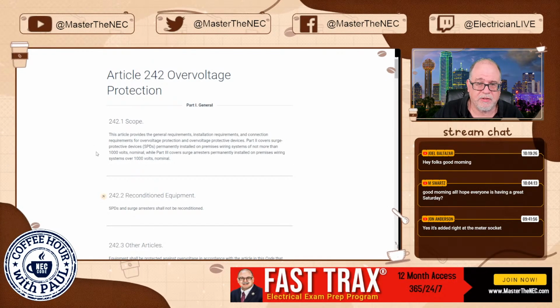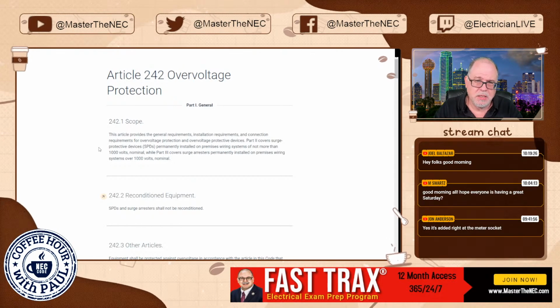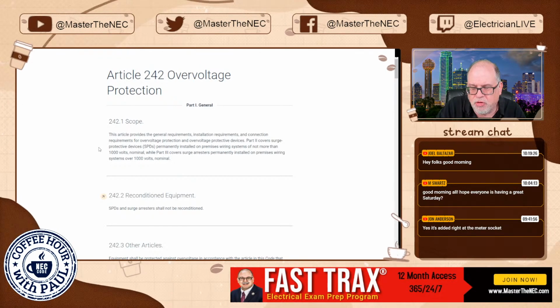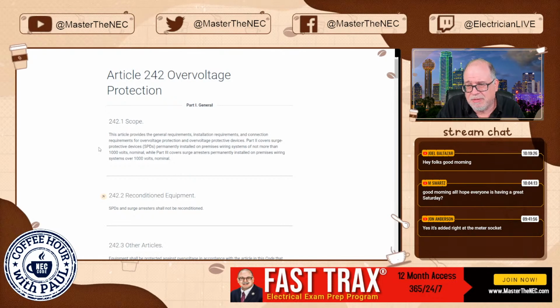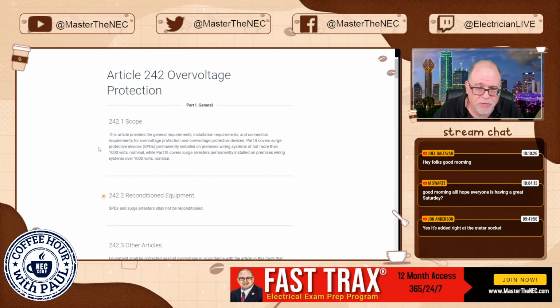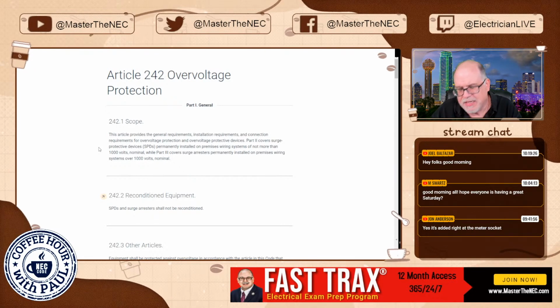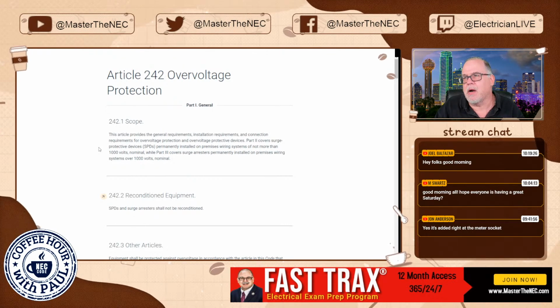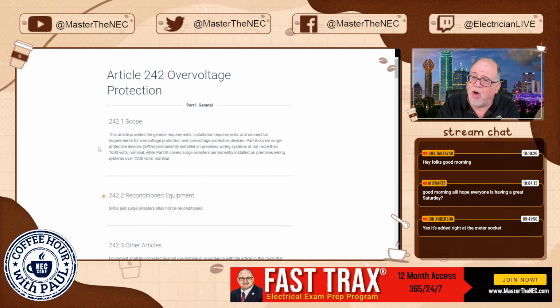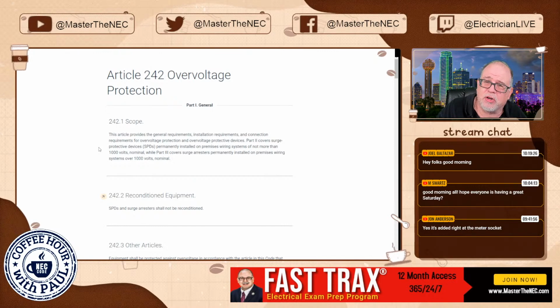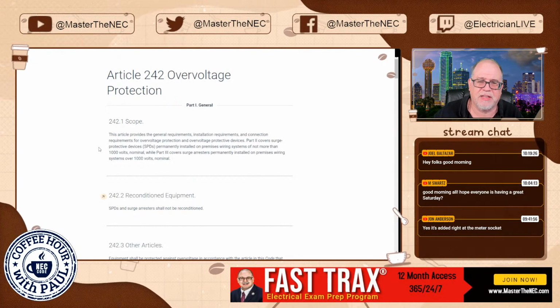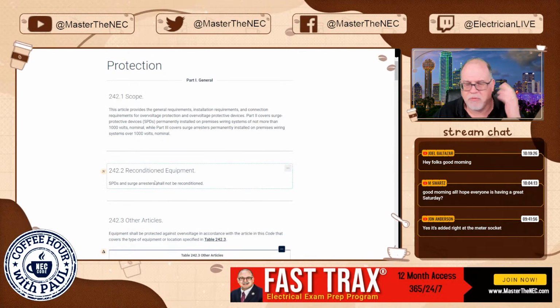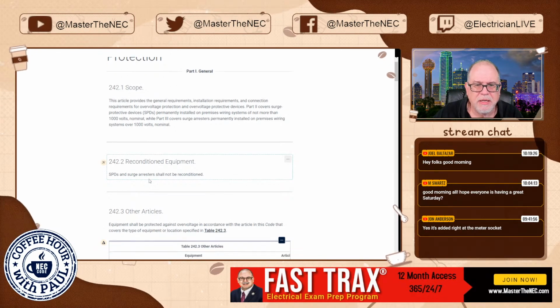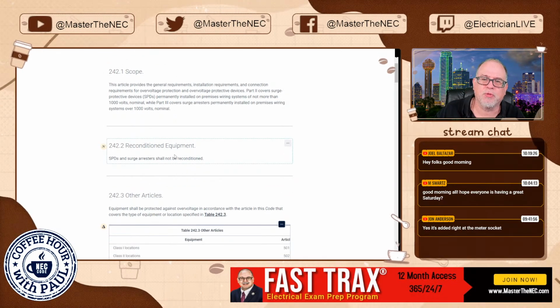Overvoltage protection. Now, y'all remember what happened here at 285, I believe, in 280, I removed here. That's surge protective devices and the surge arresters all got redone, and it's in Article 242 in the 2020 edition of the NEC. All right. Well, same here. It's not a change. And now you'll notice that we have the reconditioned equipment.